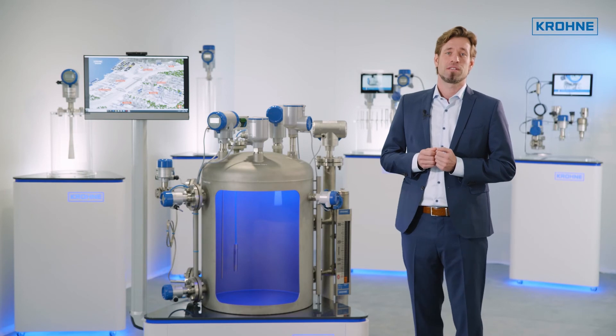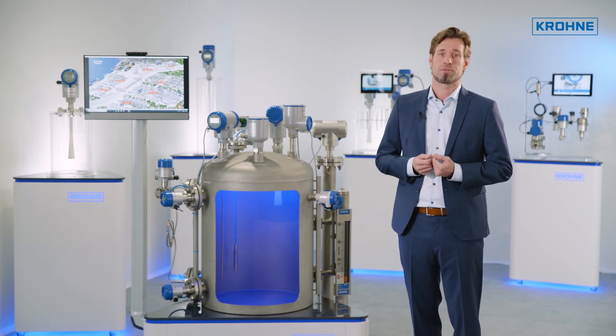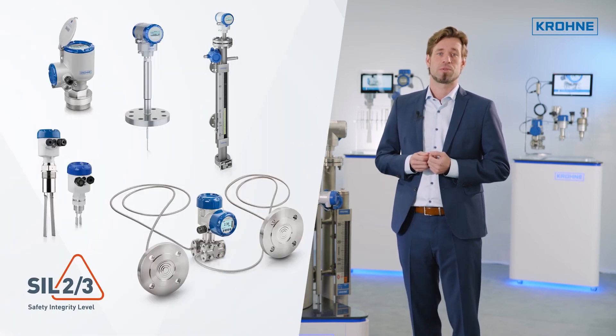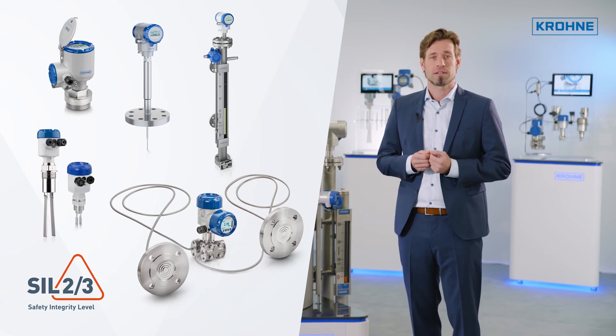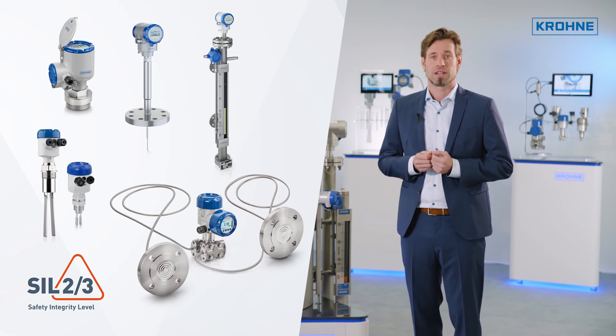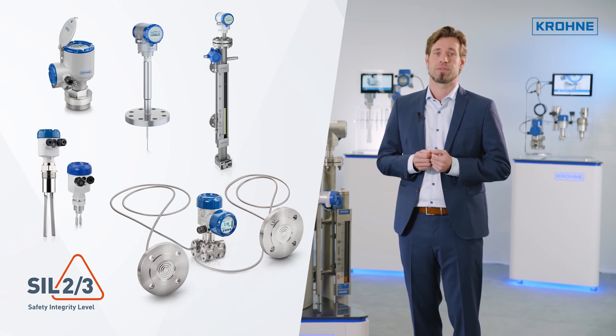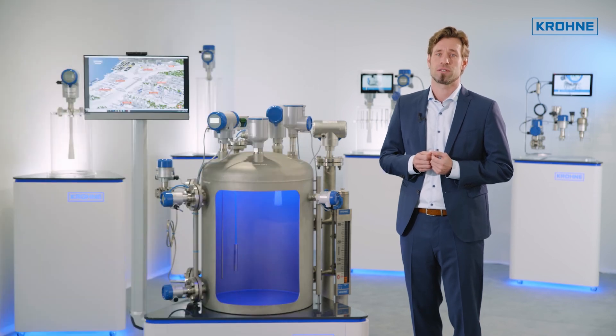KROHNE offers SIL-certified devices for safety-related applications across all measurement technologies. This includes radar units with measurement frequencies of 10, 24 and even 80 GHz, guided radars, vibration level switches, and hydrostatic level using pressure measurement technology. The devices can be used up to SIL 3 circuits in a one-out-of-two voting configuration, which means in homogeneous redundancy.